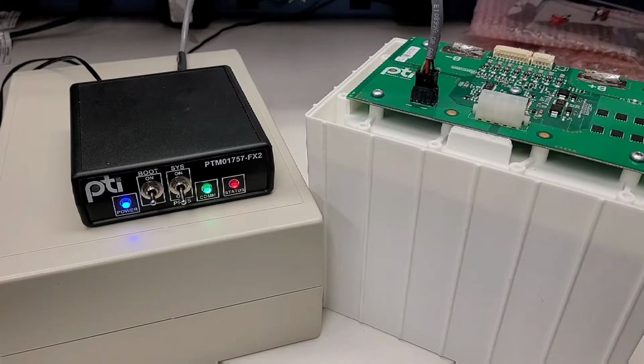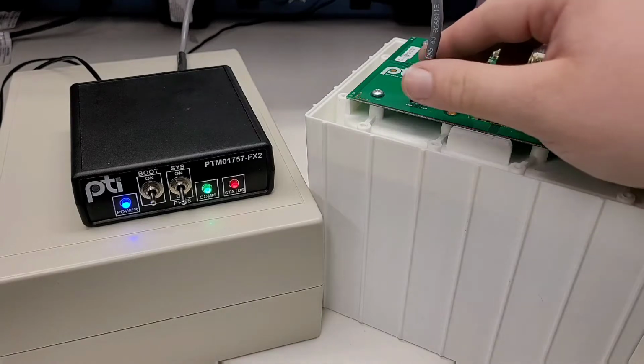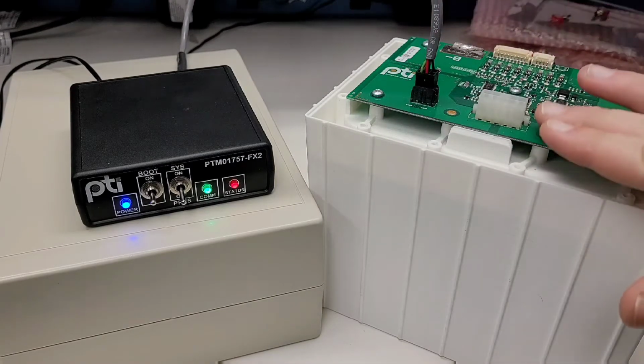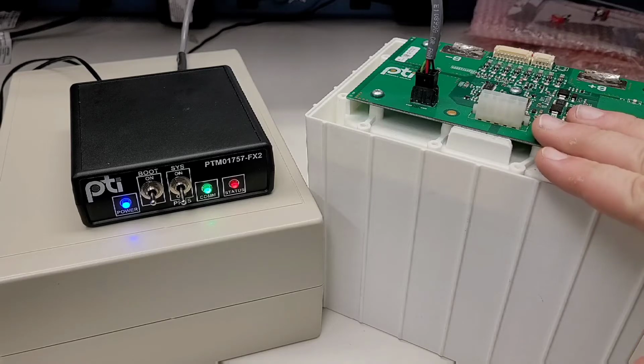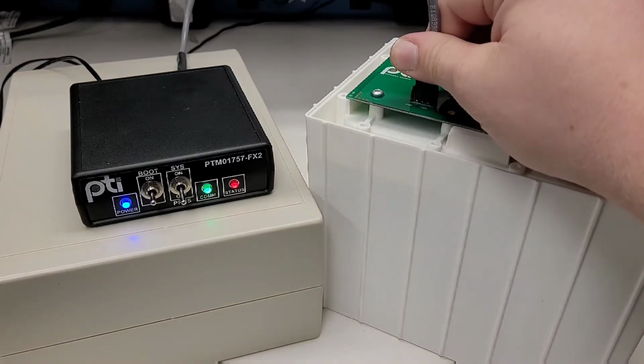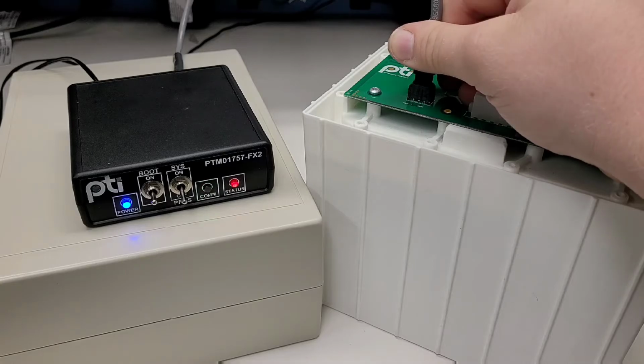This is important because, especially when working with I2C, sometimes the communications have a few minor glitches. And so you need to be able to do retries, be able to redo queries and things. So I'll demonstrate here. If for some reason some bad data is sent out by the battery pack, then it will try to redo communications. And if it can reestablish communications, then it'll go back to green and continue its test protocol. No counters will be set, no data will be erased.